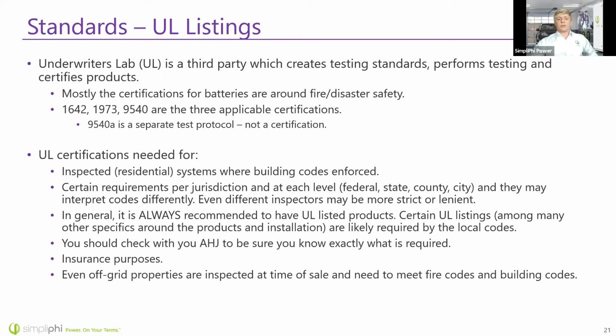UL certifications are needed mainly for residential systems, something you're going to need a permit for or that's going to be inspected. If you're getting your system inspected, they're almost definitely going to require a 1973 certification, and as time goes on, more and more jurisdictions are also requiring 9540 and some even 9540A testing.